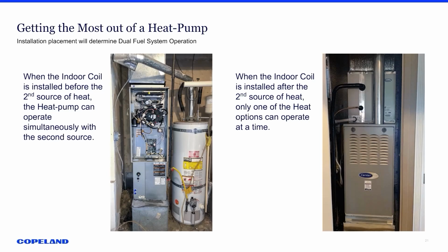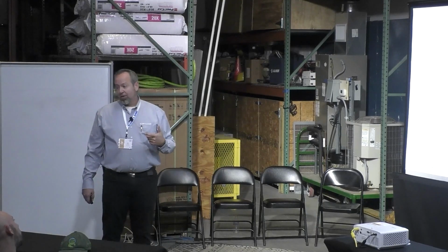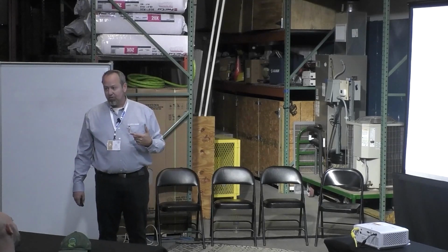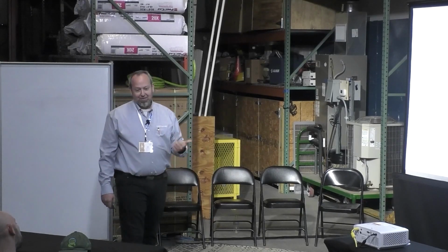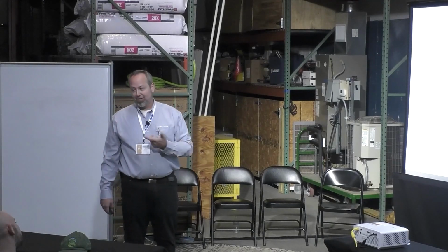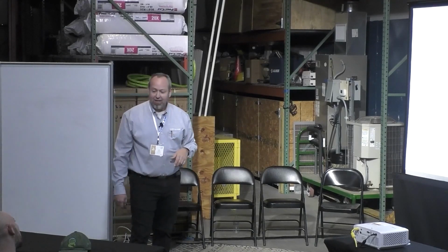If you leave your coil on top of, on your exit side of your furnace, you're going to run either your heat pump or your furnace, one or the other. You're not going to run them together. Or if you try to run them together, you run the risk of blowing a fuse, eventually taking out a compressor, or kicking out the high limits.